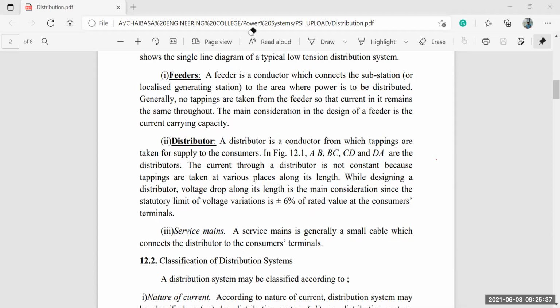You could also see a feeder definition and distributor definition, and compare the two. A feeder is a conductor which connects a substation or localized generation station to an area where power is distributed. No tappings are taken from the feeder, so the current in it remains the same throughout. The main consideration for a feeder is its current capacity.